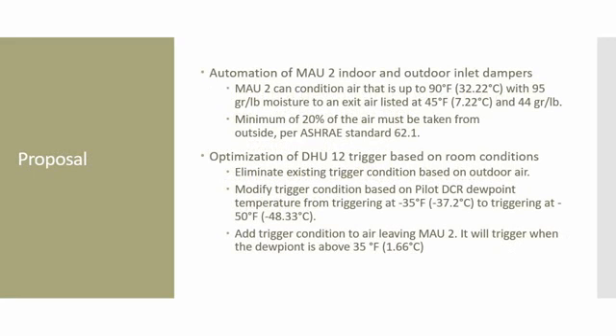We have proposed 4 solutions to optimize the current dry clean room equipment. The first solution is to automate the MAU2 indoor and outdoor inlet damper. Currently, MAU2 does not take a mixture of outdoor and indoor air. It is either one or the other. We propose to automate this. MAU2 has the capacity to take in outdoor air on a hot, humid day. Per ASHRAE standards, it is required that we take in a minimum of 20% outdoor air. This will ensure that fresh air will be circulated throughout the room, but it won't be too much outdoor air that puts a strain on the equipment.